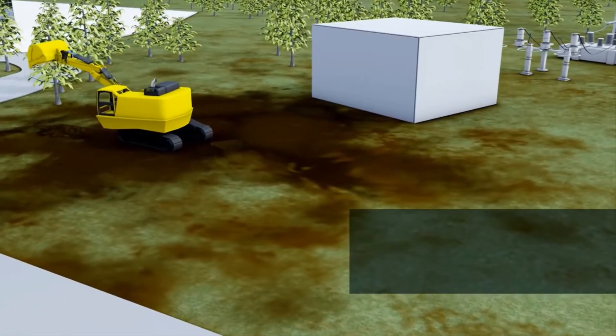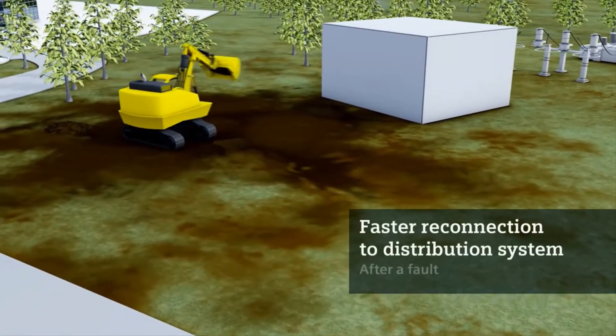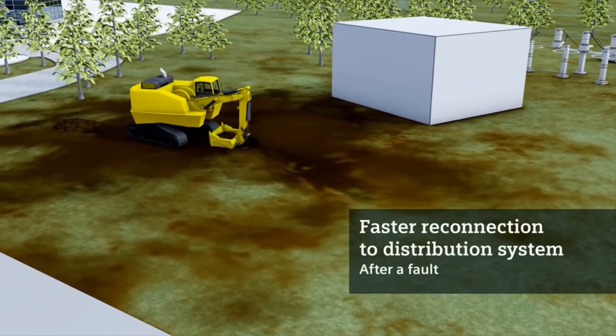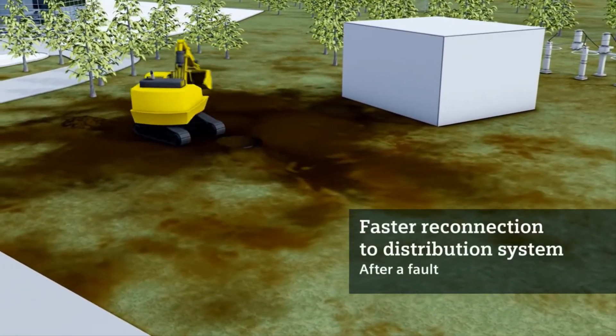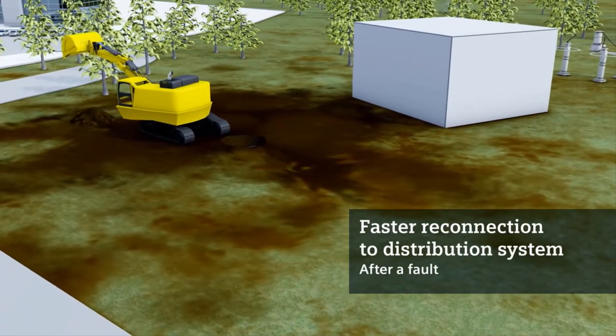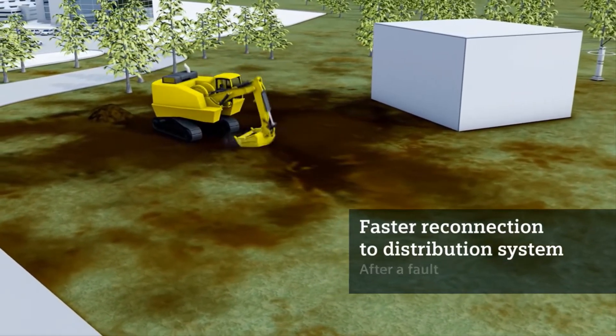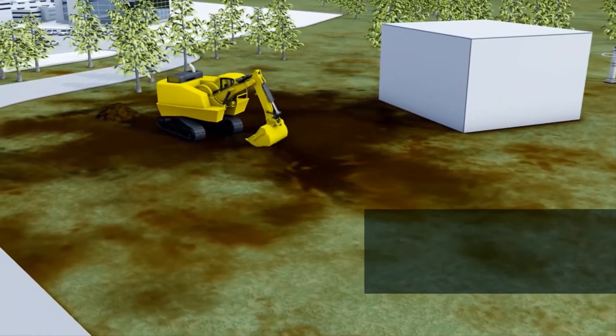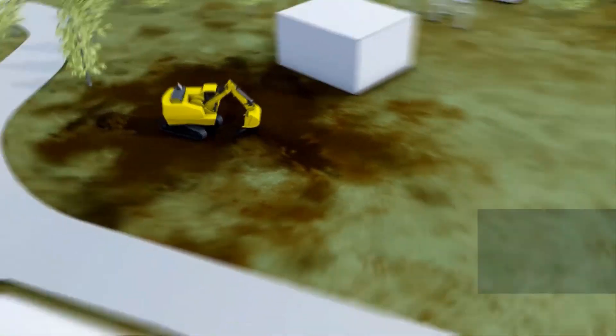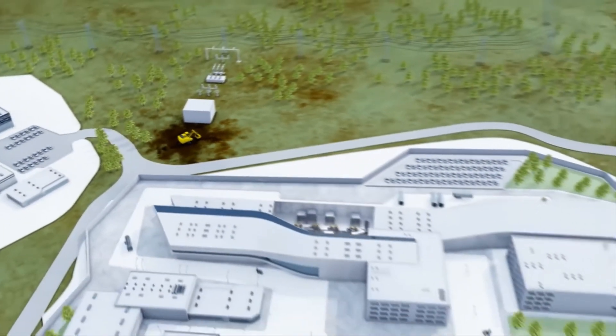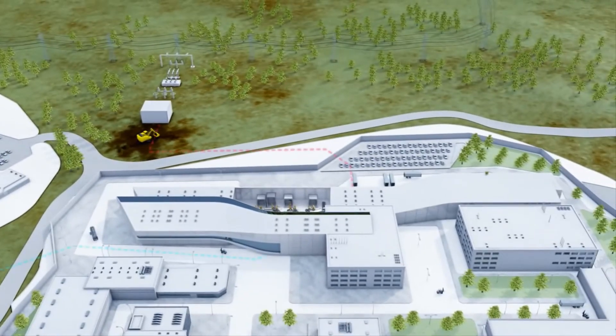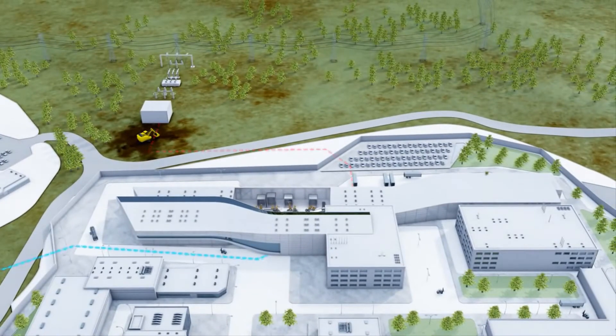By way of example, if a cable connection is destroyed during construction work, the affected switchgear panel's circuit breaker switches off the fault. The other panels, and thus all other consumers, stay in service.